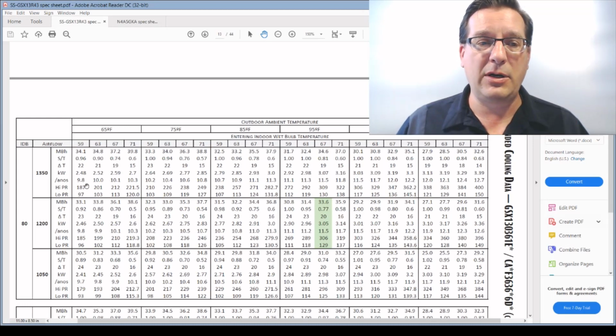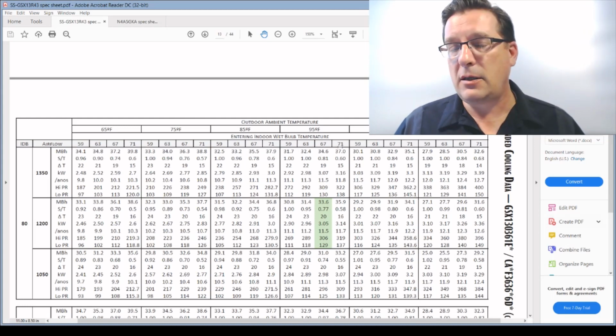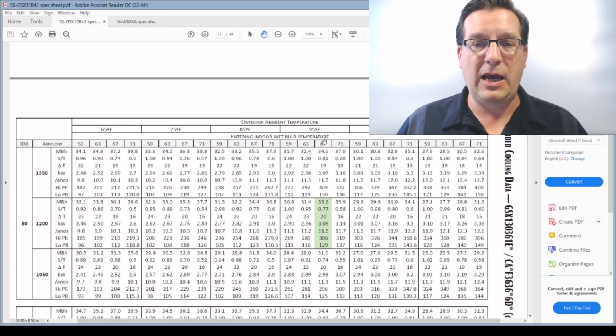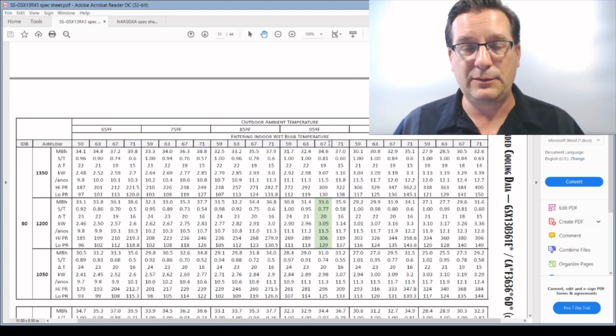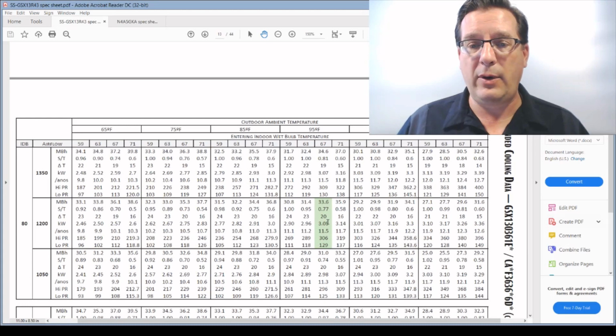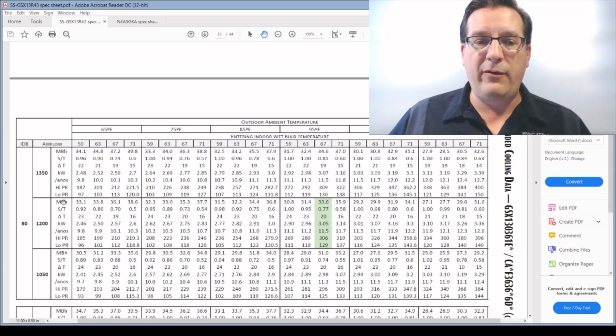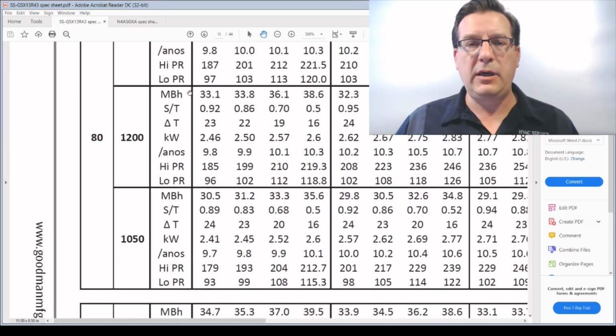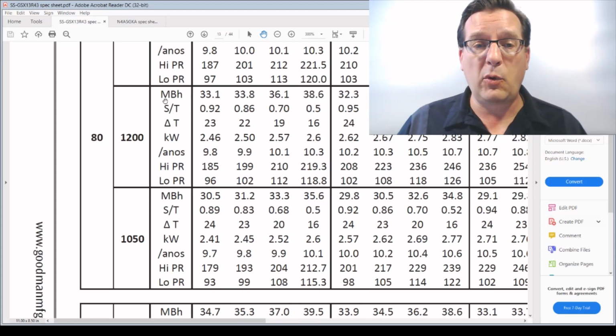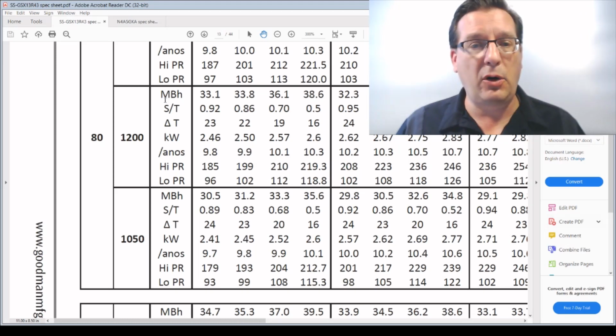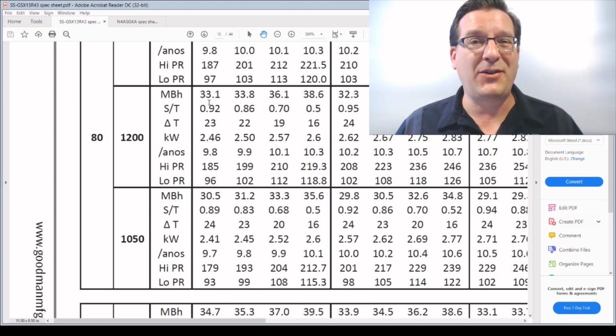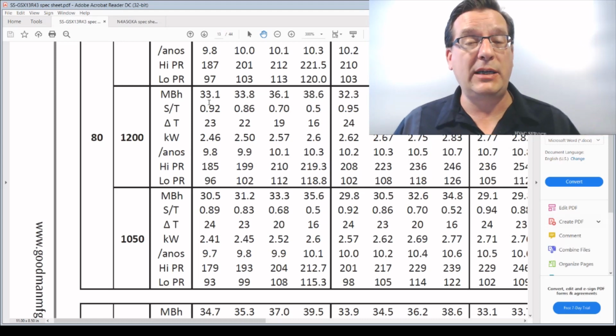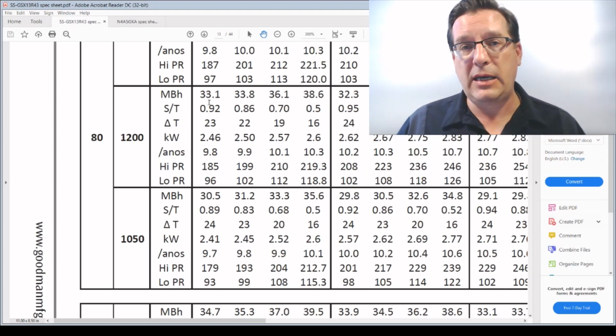As it stands here, we have an indoor temperature of 80 degrees and a variety of indoor wet bulbs at 59, 63, 67, and 71. This gives us a pretty good range of performances for this specific outdoor temp. Standard design conditions are 95 degree outdoor, 80 degree indoor, with a 67 degree wet bulb temperature. That is design condition, and that's why that is highlighted right here. So for every one of these categories, now we have a variety of specifications that are given, and here is what they are. The first performance specification given is MBH. This stands for 1000 BTU per hour. This next column over says 33.1. That means 33,100 BTU per hour. This is also known as the total heat removal capacity of this AC under these conditions.